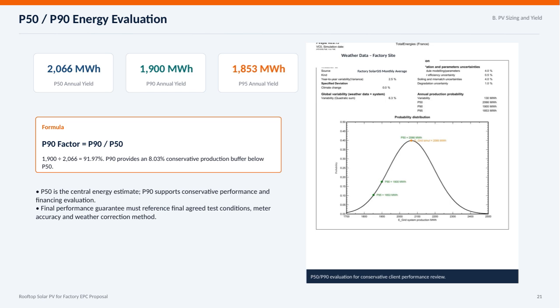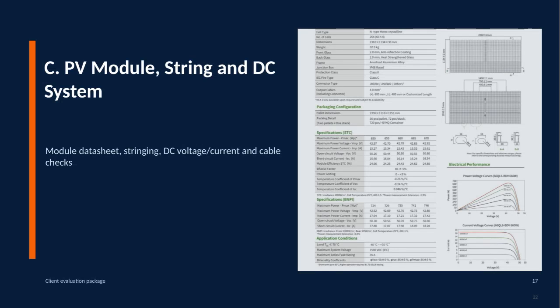It's important to note that the final performance guarantees must be based on agreed test conditions, including accurate meter readings and weather data corrections to reflect true system output. This approach gives confidence that the system will meet expectations even under less favorable conditions. Here we focus on the PV module, the string, and the DC system. This includes reviewing the module datasheet, which is essential to understand the specifications and performance parameters of the solar panels. We also cover stringing, which refers to how individual modules are connected electrically, affecting the overall system voltage and current. It's crucial to perform thorough DC voltage, current, and cable checks to ensure system safety and efficiency. Lastly, we provide the client evaluation package, which summarizes all these technical details for client review and approval.